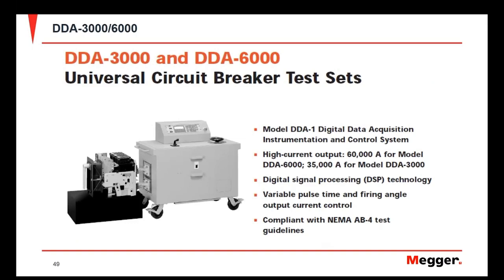Another instrument for primary injection testing is the DDA, available in the DDA 3000 and DDA 6000. The difference is the output current: the DDA 3000 provides up to 35,000 amps and the DDA 6000 up to 60,000 amps. Both are operated via the DDA 1, a digital interface for breaker testing. The DDA offers variable pulse time and firing angle to negate the challenges of primary injection testing, and is compliant with NEMA AB4 breaker testing guidelines.